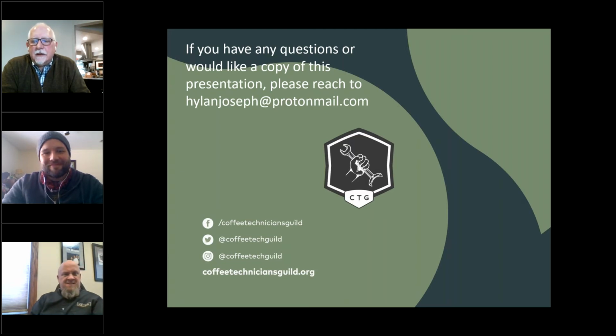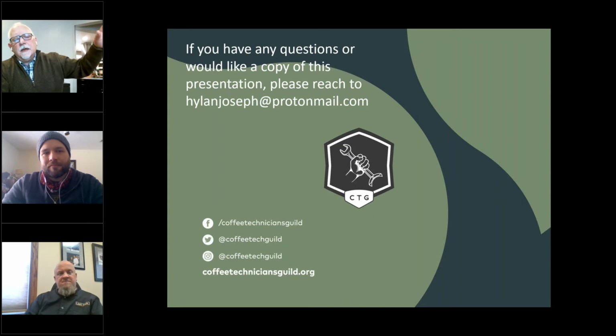Sorry, go for it, Mike. Electricity is like water. You've got water flowing to the shower, and then someone flushes the toilet, and the water pressure drops. So if you've got an espresso machine with the heating elements on, drawing 208 volts, and then a big baking oven comes on close to the same circuit, that's going to create an excessive load and drop the voltage everywhere. So that low voltage of 200 volts that's messing with the machine may not even happen while you're there, but it's happening at some point. In that case, you can actually put a buck and boost transformer on it and take it up to 230 and be safe. But that's a whole other issue.